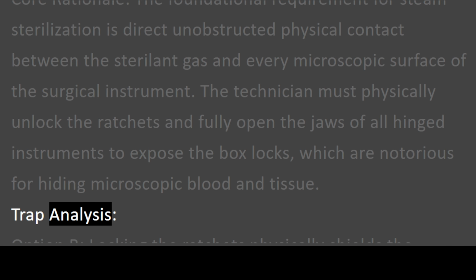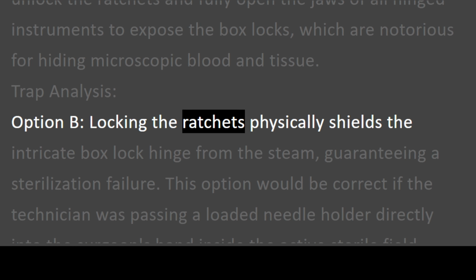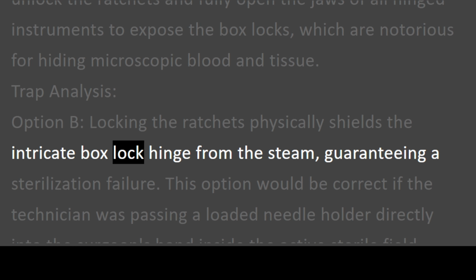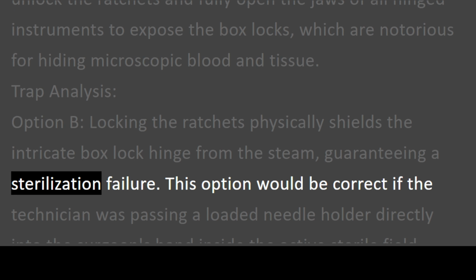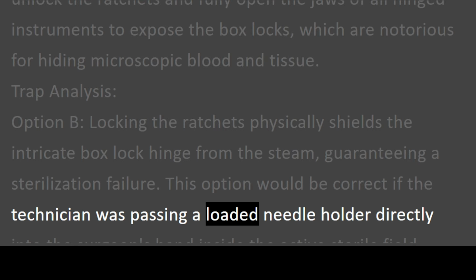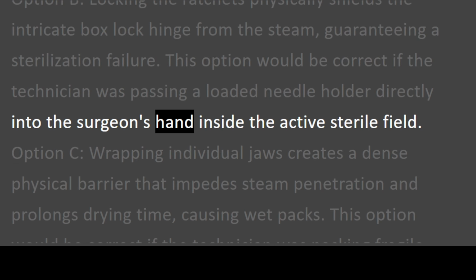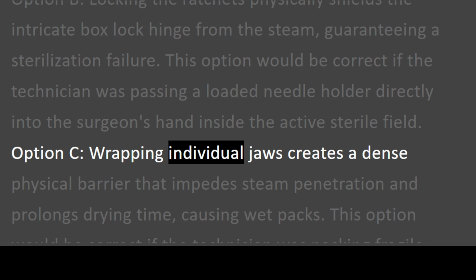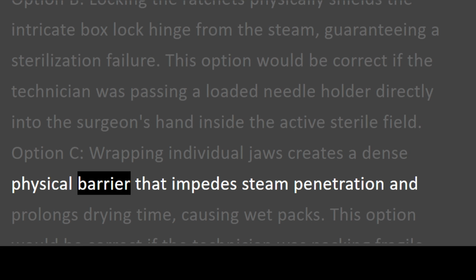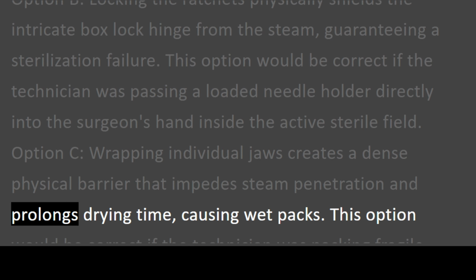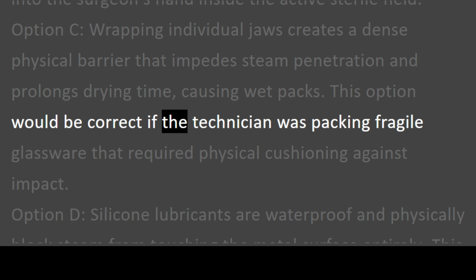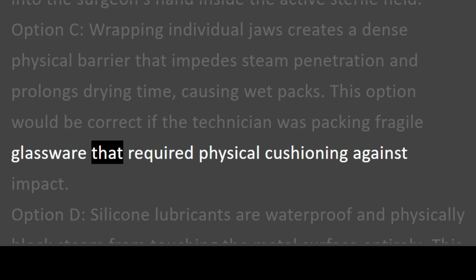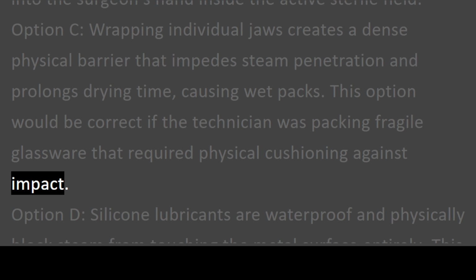Trap analysis. Option B. Locking the ratchets physically shields the intricate box lock hinge from the steam, guaranteeing a sterilization failure. This option would be correct if the technician was passing a loaded needle holder directly into the surgeon's hand inside the active sterile field. Option C. Wrapping individual jaws creates a dense physical barrier that impedes steam penetration and prolongs drying time, causing wet packs. This option would be correct if the technician was packing fragile glassware that required physical cushioning against impact.